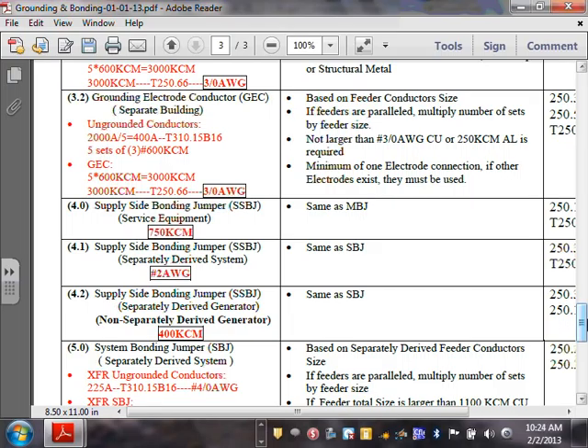The lugs have to be rated for that too, the grounding lugs and grounding clamp and all this stuff. Does anybody do it this way, like a copper bar going across all of them? I don't know if there's an approved fitting for it. If you find UL approved fittings that bond them all with one copper bar, I don't see why not, and take them all the way as a bar, but the problem is the fittings. Okay, any comments, guys? Any questions about a supply side bonding jumper? Do you guys want a 5 minute break before we move on? Okay, let's take 5 minutes.